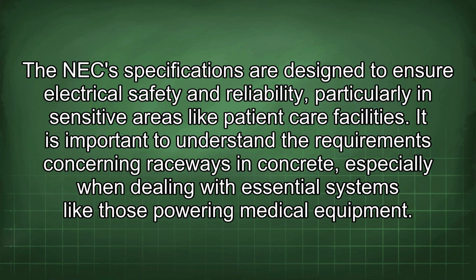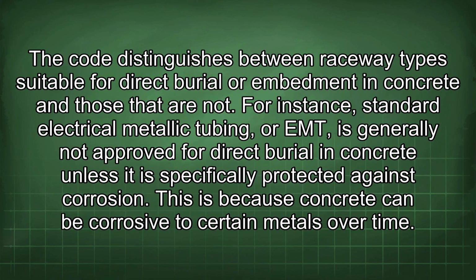It is important to understand the requirements concerning raceways in concrete, especially when dealing with essential systems like those powering medical equipment. The code distinguishes between raceway types suitable for direct burial or embedment in concrete and those that are not. For instance, standard electrical metallic tubing, or EMT, is generally not approved for direct burial in concrete unless it is specifically protected against corrosion. This is because concrete can be corrosive to certain metals over time.